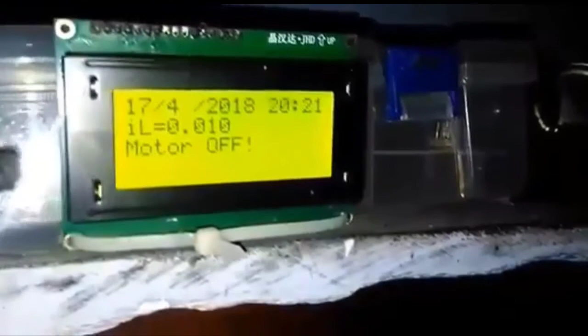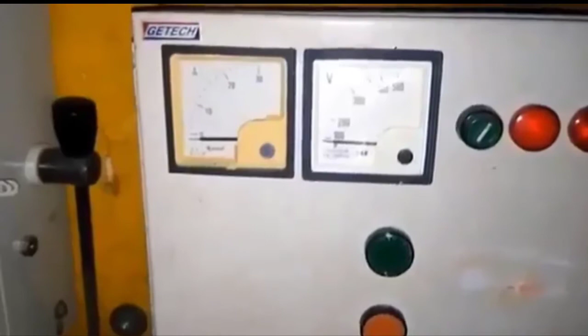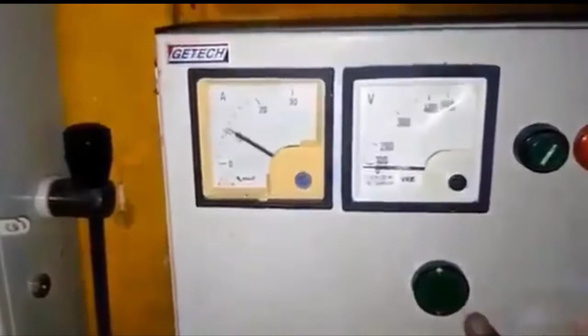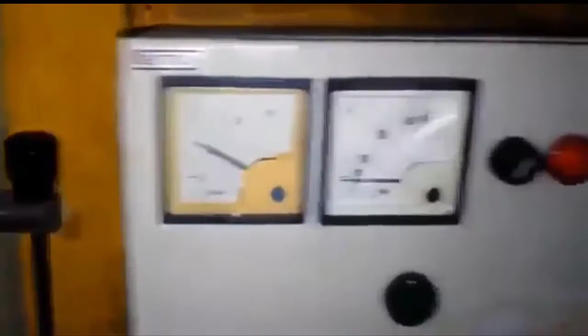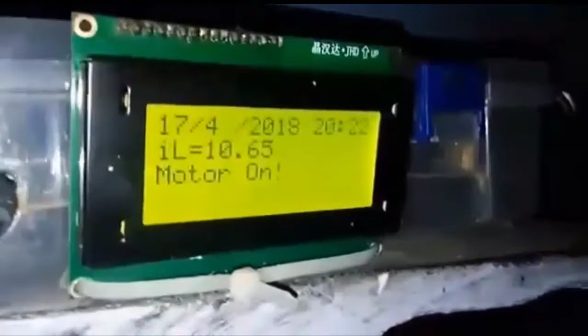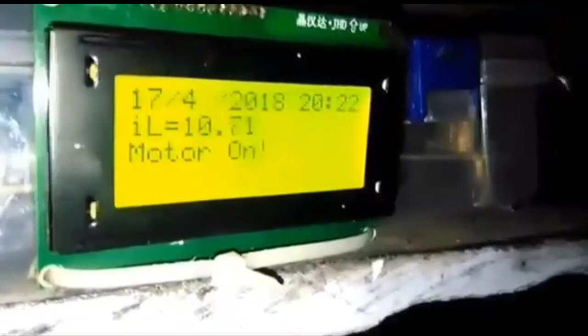On the LCD I have date and time, load current, and motor on/off status. Now I am going to turn on my motor. This is the start button. Once I turn on the motor, the current value is 10.2, and on my main controller you can see the current values at 10.64, floating around 10.68275, and the motor status is on.